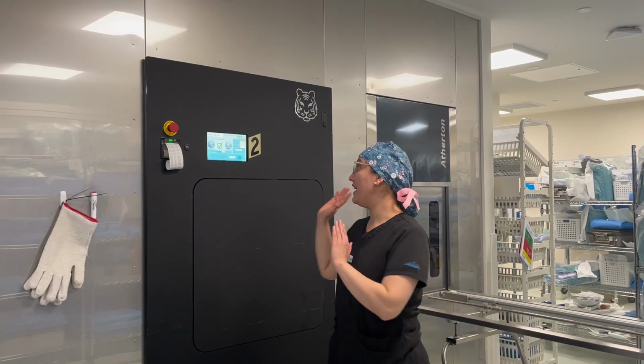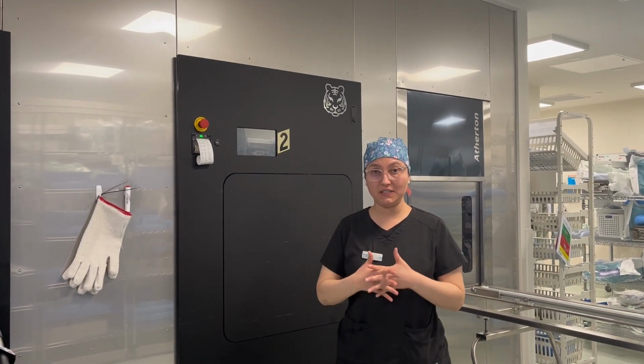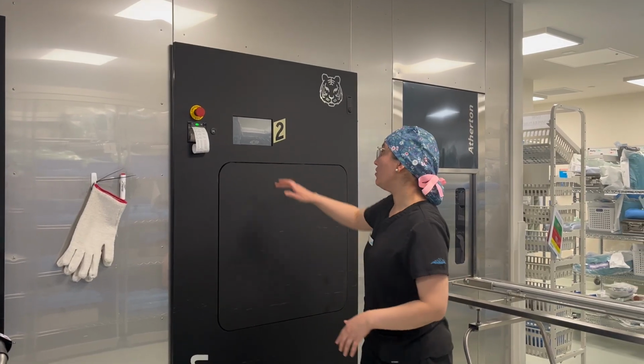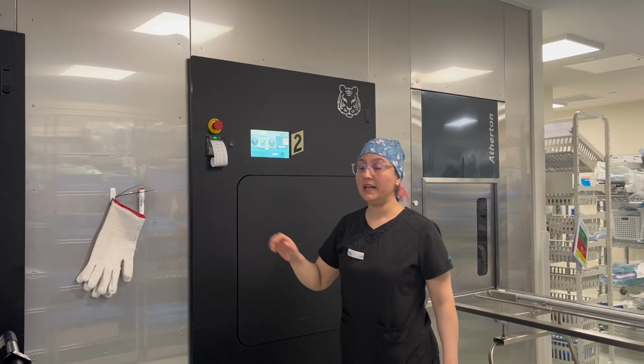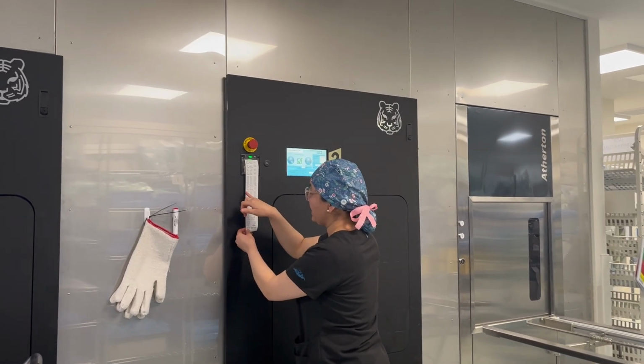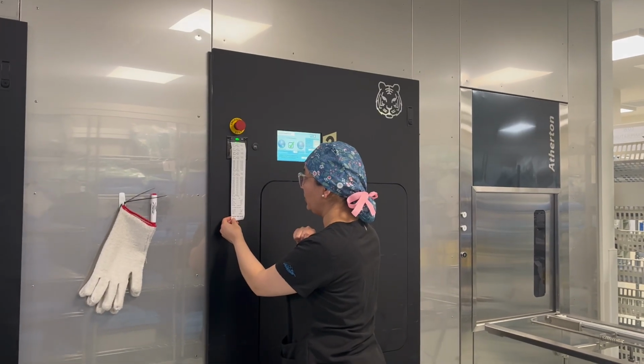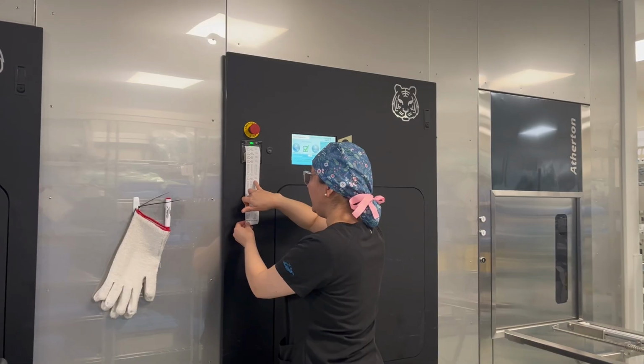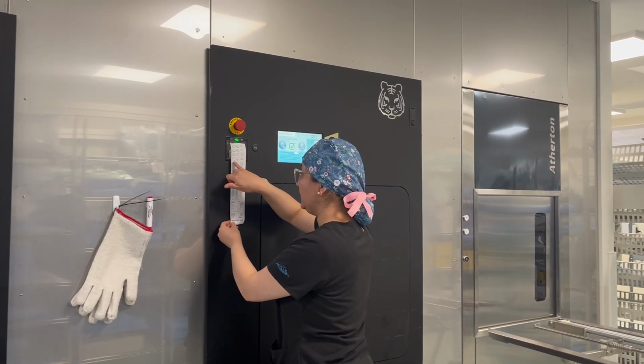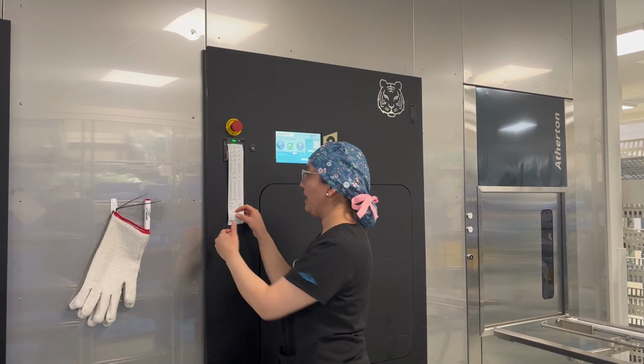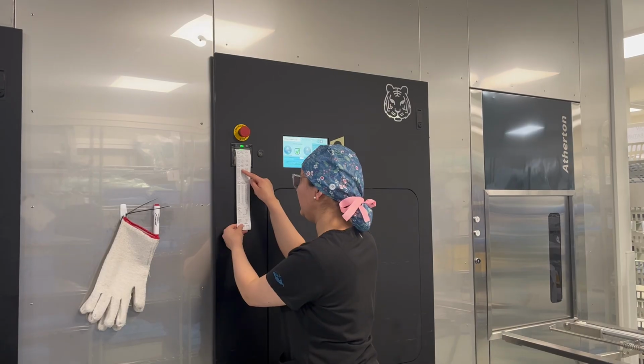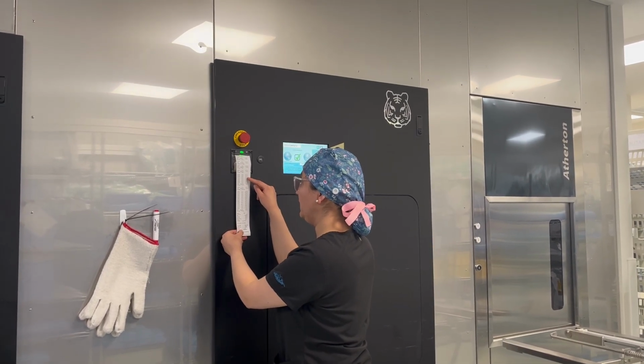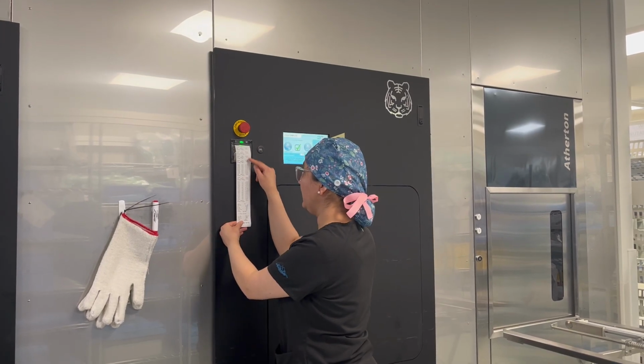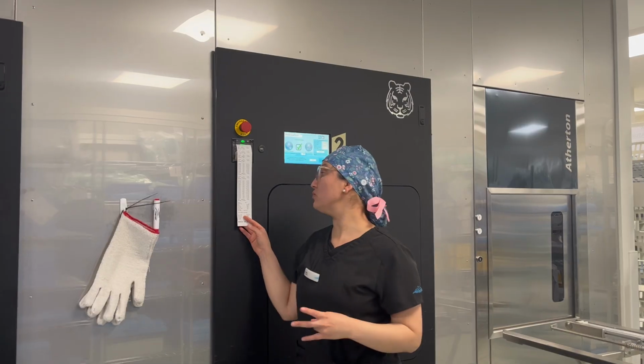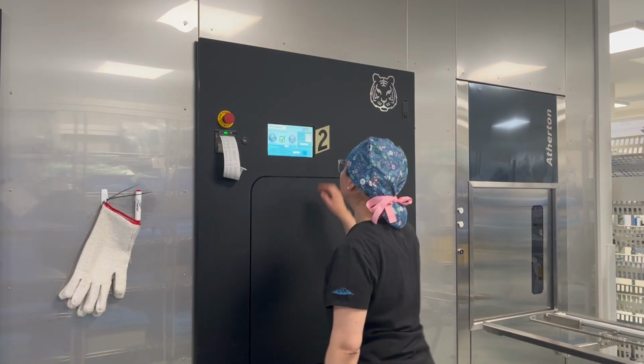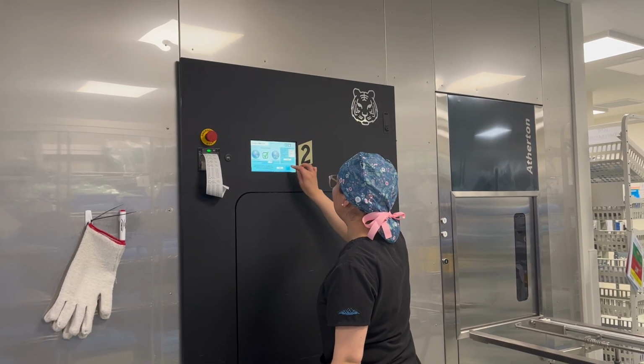Hi, this is the end of the cycle in the sterilization process where we have 4 power tools. So I'm going to approve the cycle, but before releasing the load, I need to check here if it's the right time, the temperature, and the pressure. As we can see here, it is right. The temperature is above 134 degrees, it's 135 degrees. The pressure was 215 kilopascals, and the holding time for the sterilization process was 4 minutes, which is what is in the standard, and the cycle is passed. So I'm going to take the load out of the autoclave.